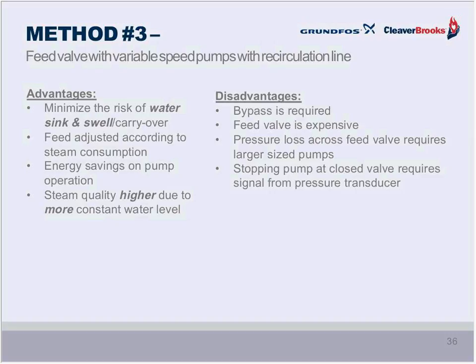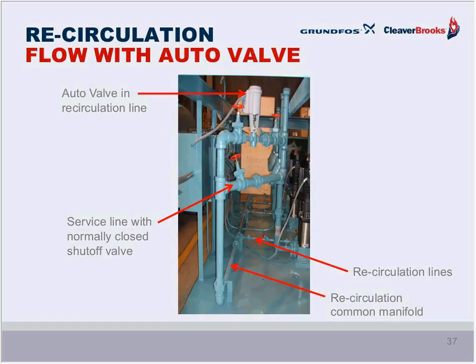The pressure loss across the feed valve does often require a larger size pump, and then you've got the addition of a transducer in your system. So there are some pros and cons to each of these methods. Just a quick word on another device that can be used with that particular control method. In those conventionally designed systems, we had an orifice recirculation line. And it doesn't matter whether it's for a fixed or a variable speed pump.